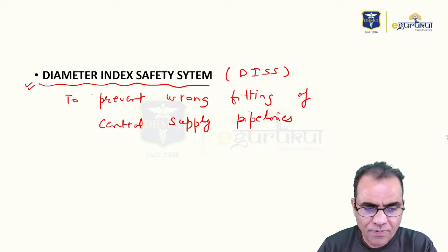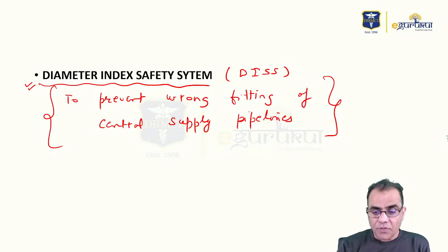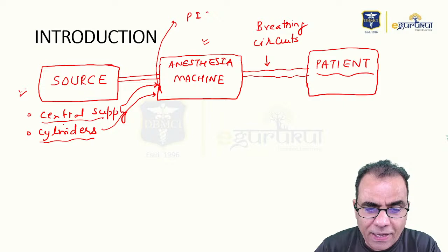So these two are very important systems. Diameter index safety system to prevent wrong fitting of central supply pipelines, and pin index system to prevent the wrong fitting of cylinders. So here, when this central supply or cylinder is attached here, what is the most important thing? That is the pin index system and diameter index safety system. This and this we normally say. Pin index system and diameter index safety system prevent the wrong fitting of cylinders and central supply.